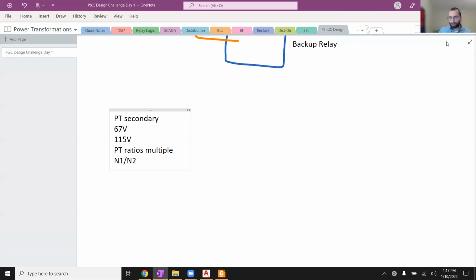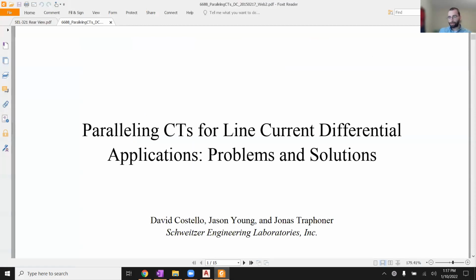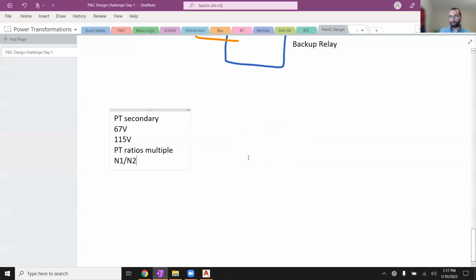Hey, Josh, question on PT ratios. I've seen a lot where the secondary voltages or primary voltages that are displayed on the nameplate are really taken as what it's rated at, not so much what it's actually going to give you. So how do you tell the difference of what the actual PT ratio is? Because you can get a ratio that might be 980 something to 1, and you just go ahead and pick it at 1,000 to 1.